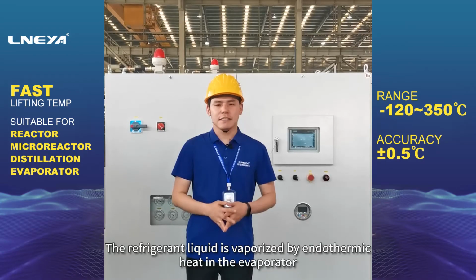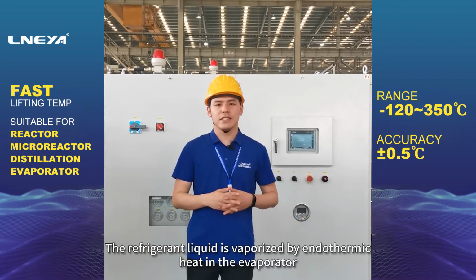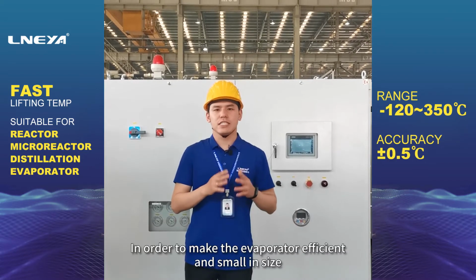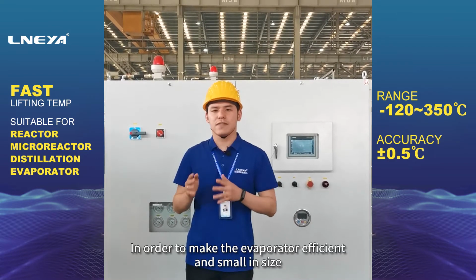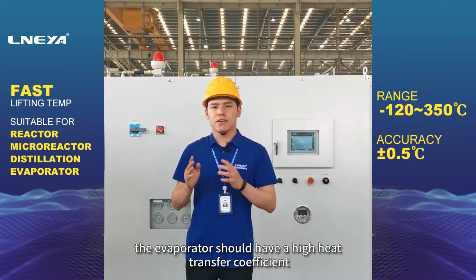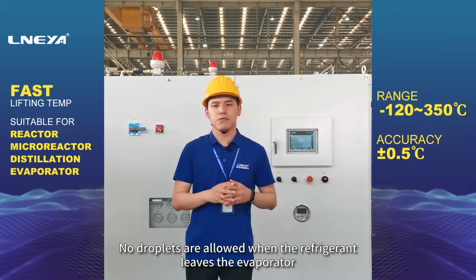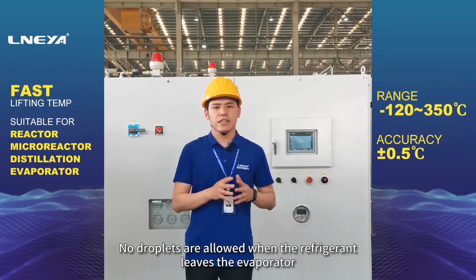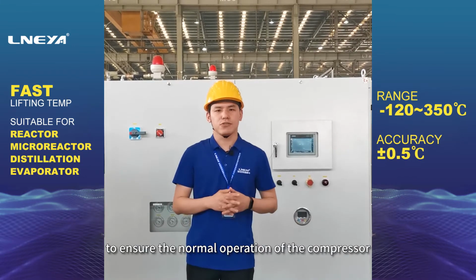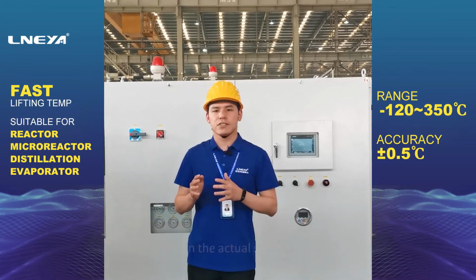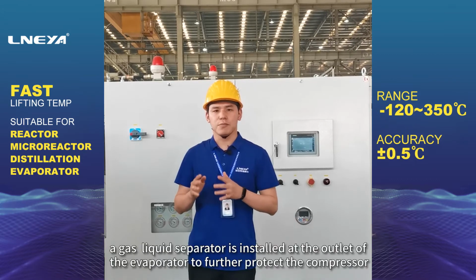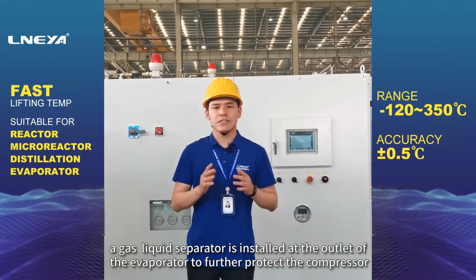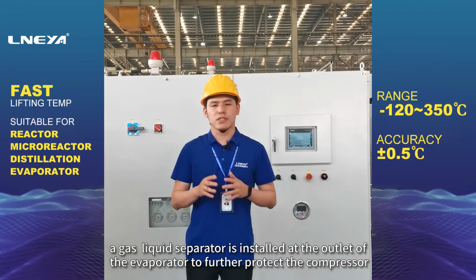The refrigerant liquid is vaporized by endothermic heat in the evaporator. In order to make the evaporator efficient and small in size, the evaporator should have a high heat transfer coefficient. No droplets are allowed when the refrigerant leaves the evaporator, to ensure the normal operation of the compressor. In the actual system, a gas-liquid separator is installed at the outlet of the evaporator to further protect the compressor.